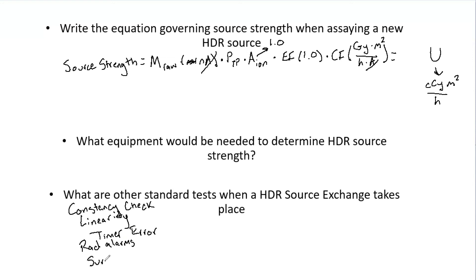Obviously, you want to do a survey of the room, you want to verify transfer tubes and all the equipment is not broken. And then finally, a power check to verify that if your clinic loses power, the afterloader will be able to continue for 15 minutes or whatever it may be.